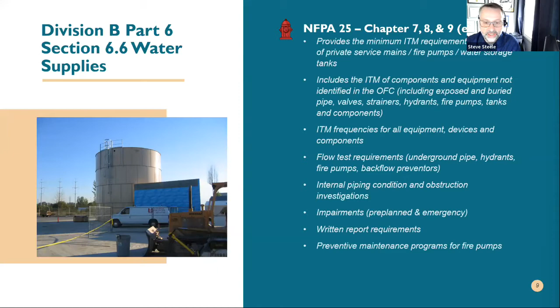Internal pipe condition and obstruction investigation, similar to the above ground systems, and with the impairments as well. Written report requirements, a lot more documentation, not just a certificate like we were used to for the past 20, 25 years saying that it passed or somebody looked at it. You have that quantifiable, and those results and that data at your fingertips as well. Preventive maintenance programs for fire pumps, so minimum things to do to ensure, not just waiting for the next annual test. And we'll get into that as far as the OFC.